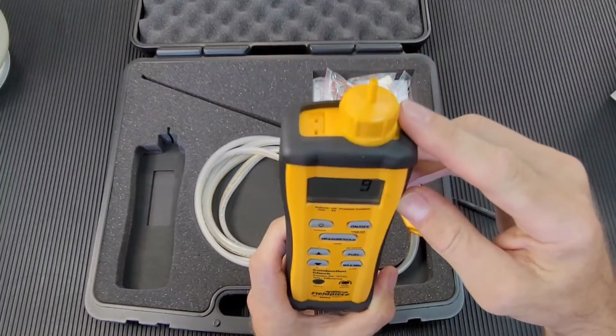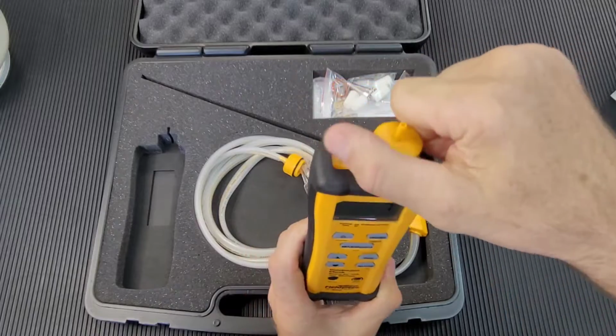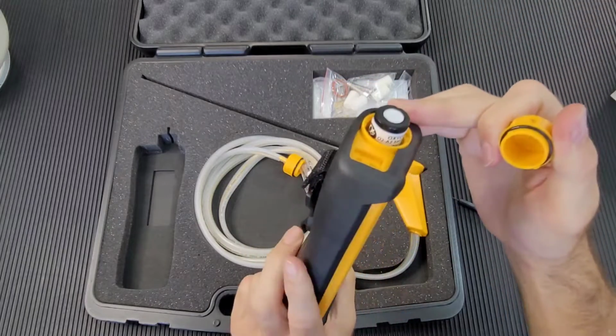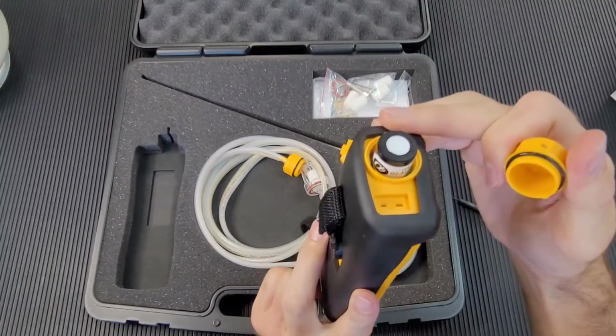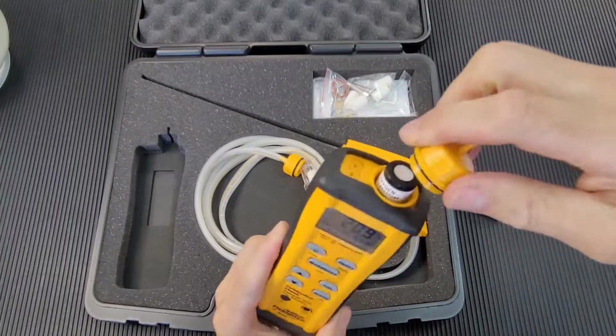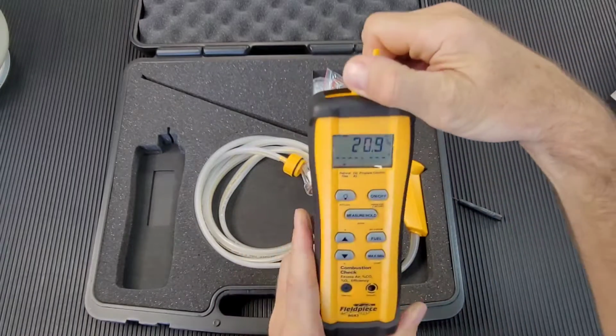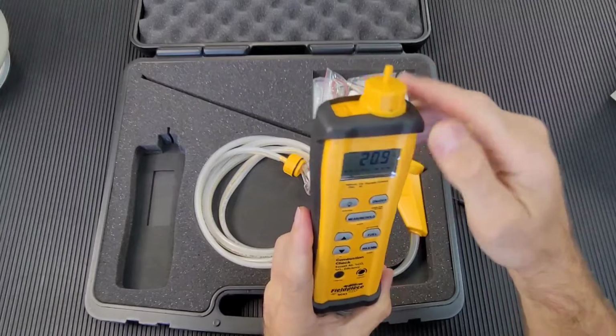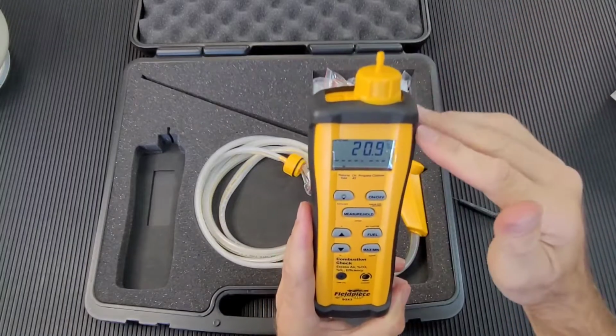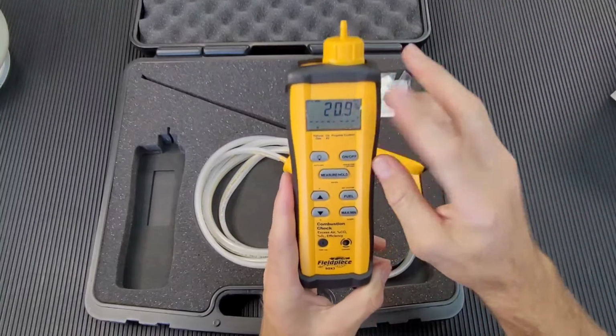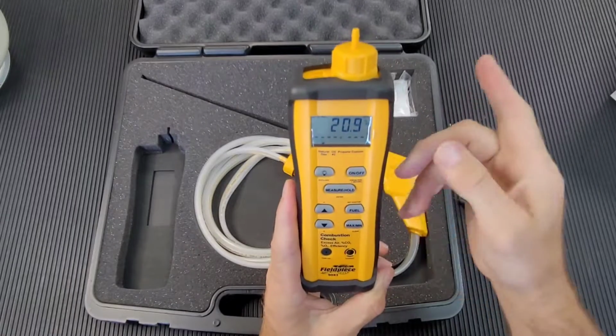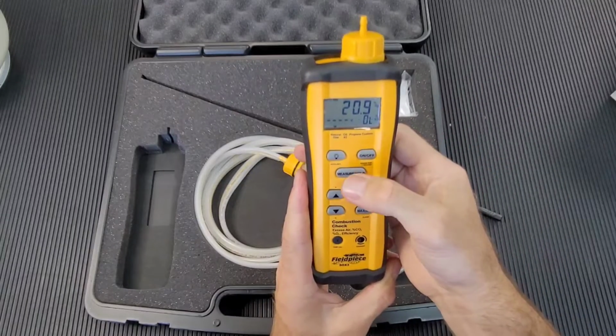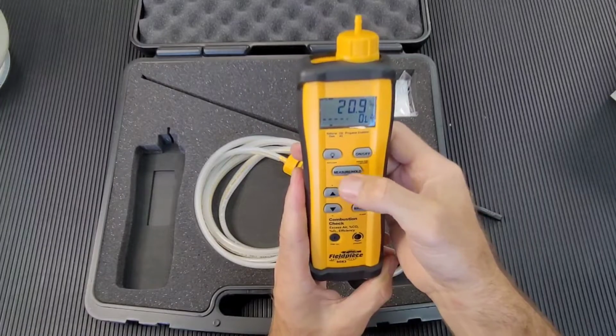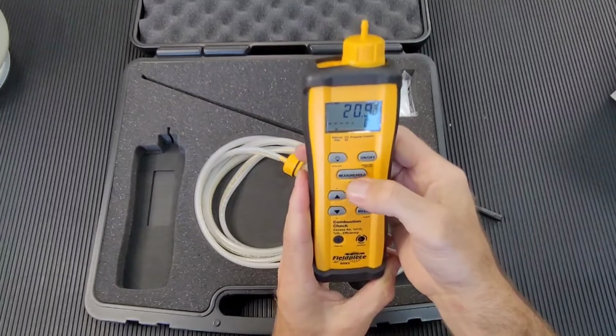You could hear the pump running, and in the little cap here is the sensor. It's the alpha sensor, folks, the O2A2. Okay, it's a very, very famous sensor, proven itself over the many years it's been available to us. So in terms of quality of sensor, one of the best on the market, okay? 20.9, and the pump has stopped. If you want to take a measurement, the pump is on. Hold, pump is off. Pump is on, pump is off.